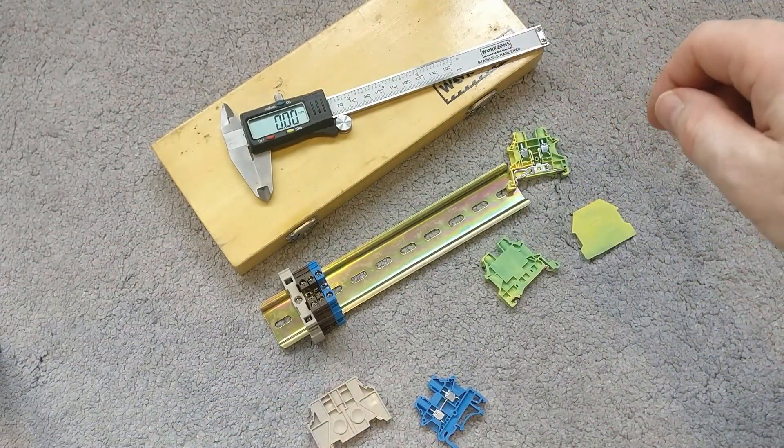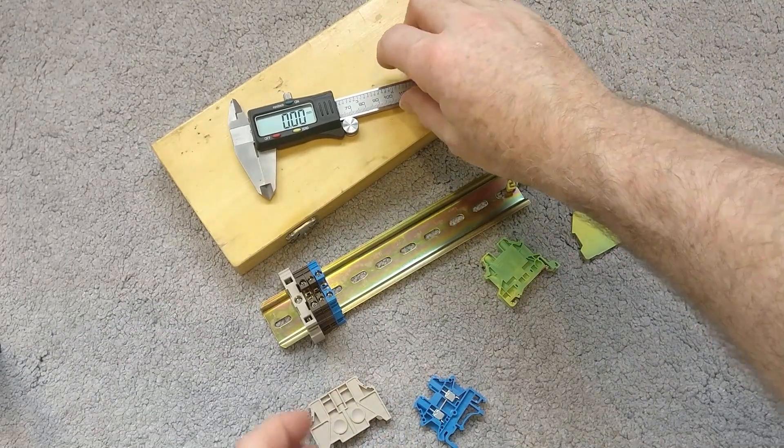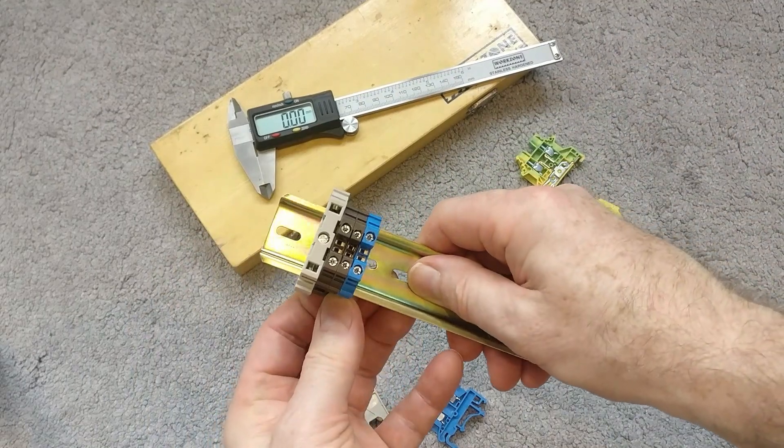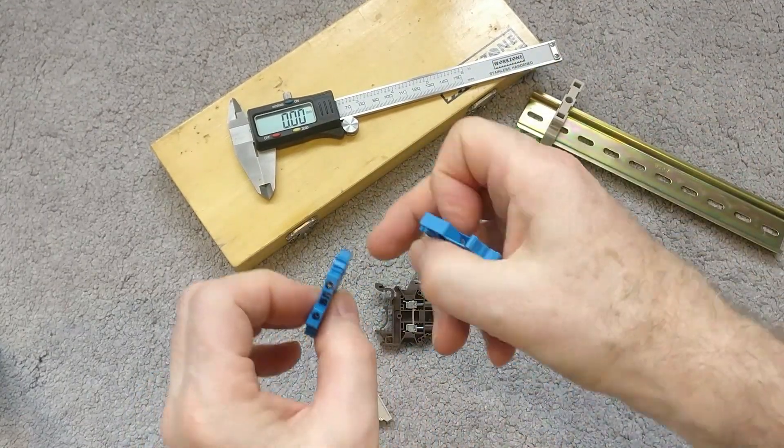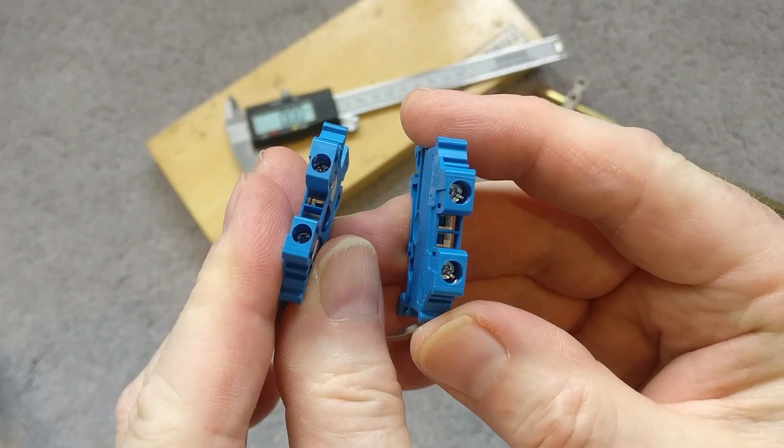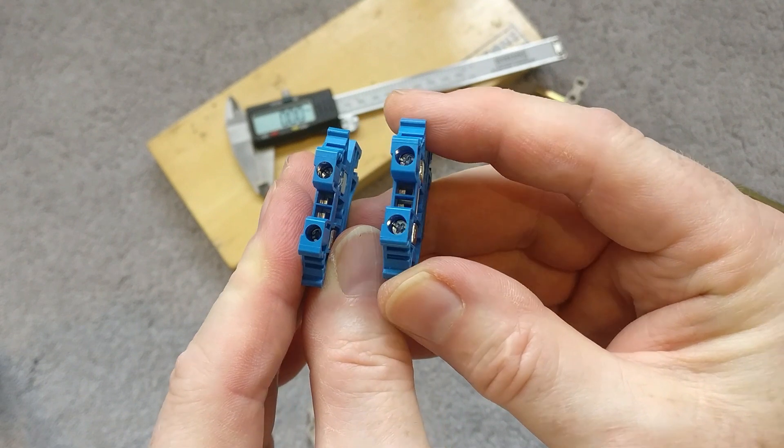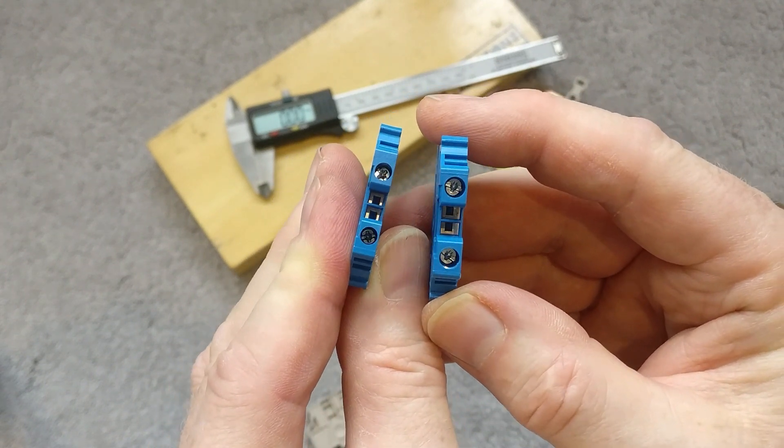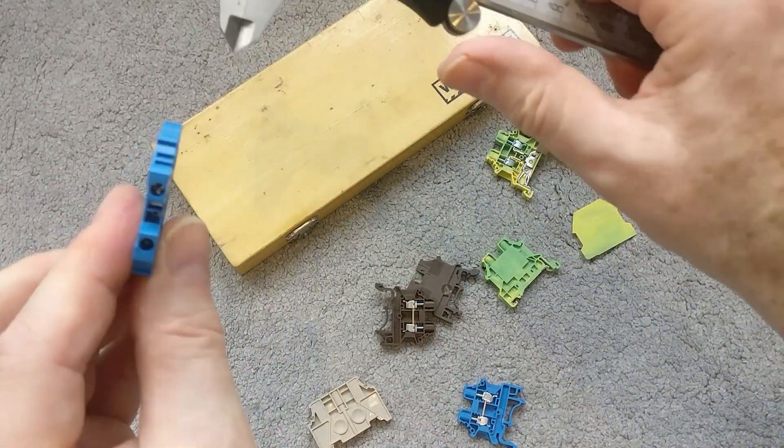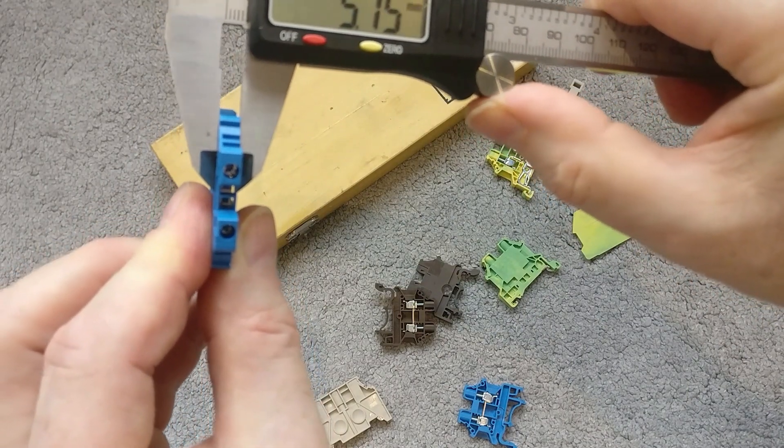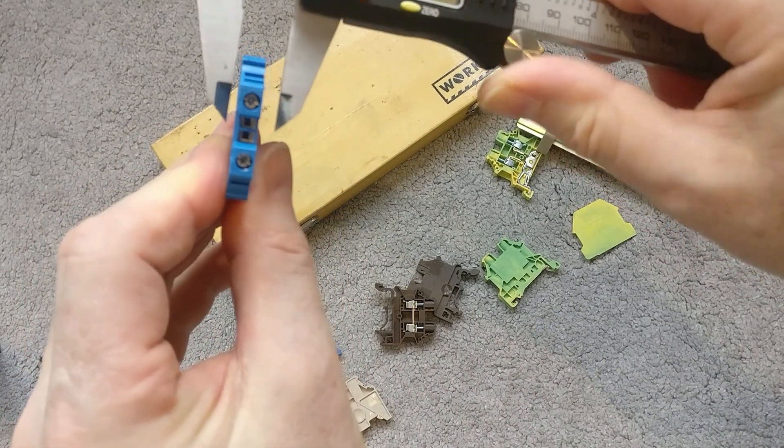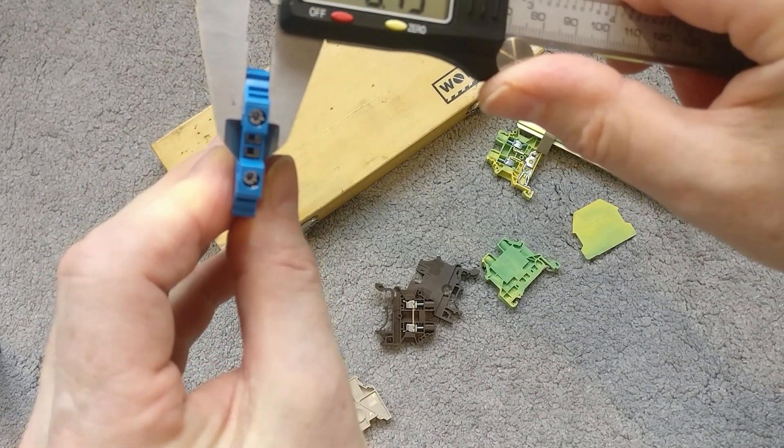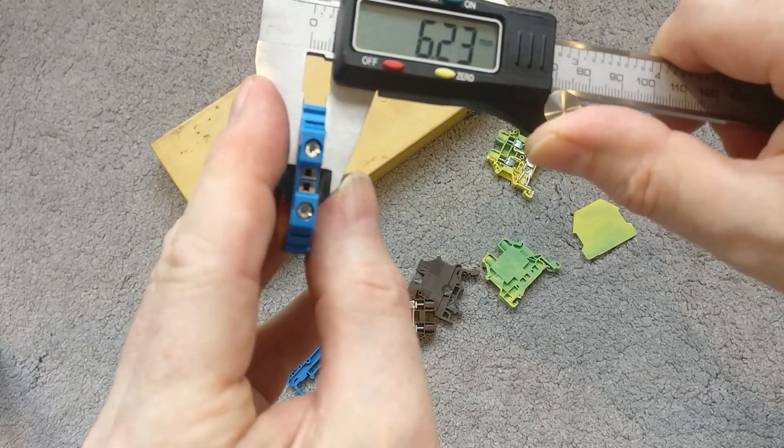Anyway, I hope that gives you a bit more of a detailed overview. Oh, one thing we didn't do was compare the two whether you've got a 4mm or a 2mm. The one on the left here is a 2mm squared, that's about 16 amps, and the one on the right is 4mm squared, that's about 30 to 32 amps. So if I just do a comparison of the thicknesses, the 2mm squared is 5mm thick, and then if we take the 4mm squared, they are 6mm thick. So only just a millimeter difference to give it that little bit extra in terms of current carrying capacity.